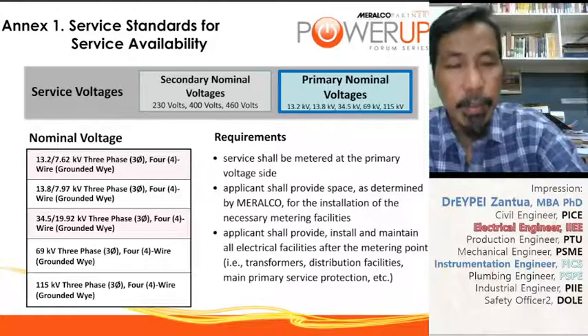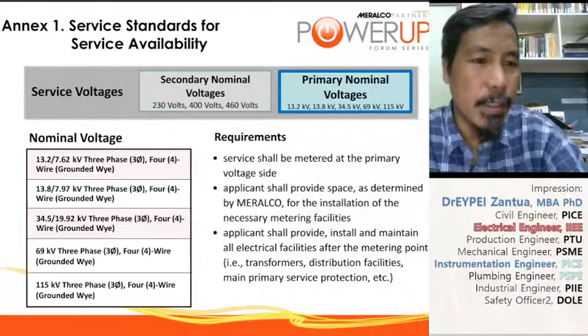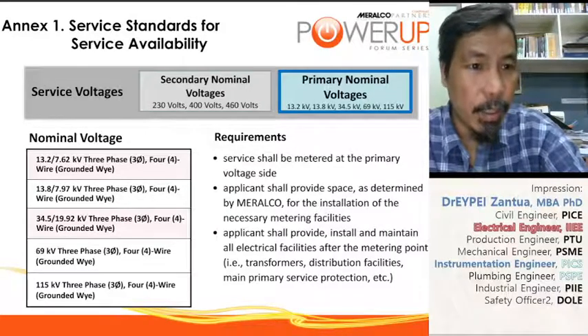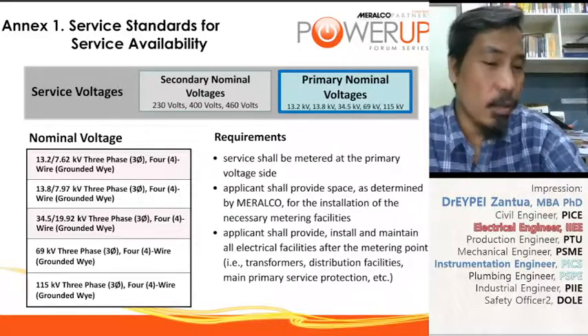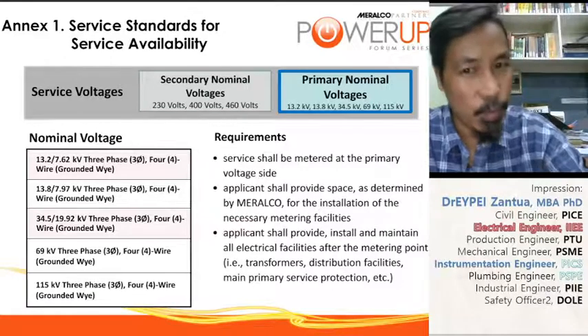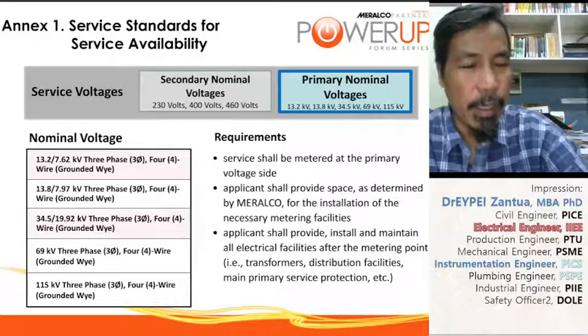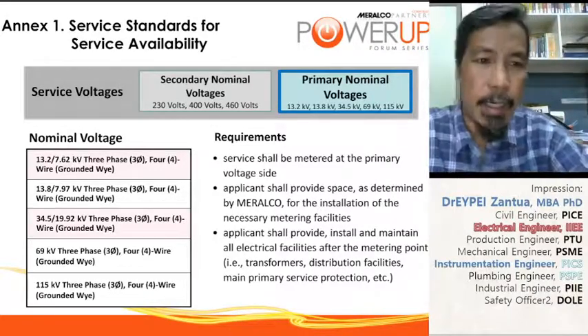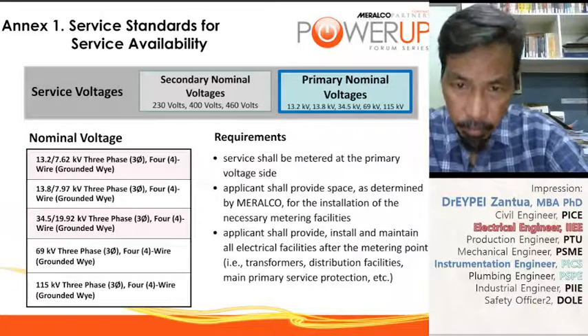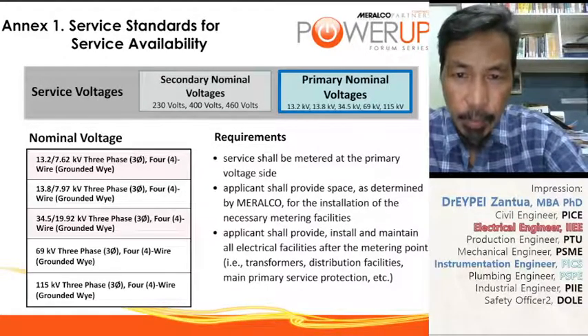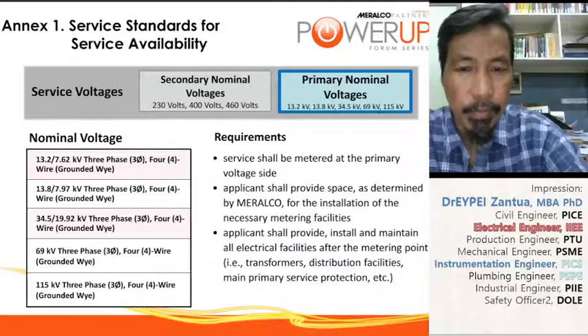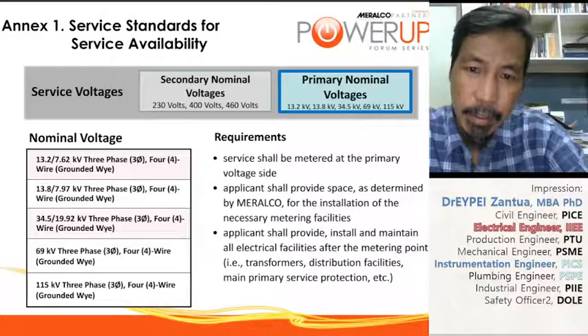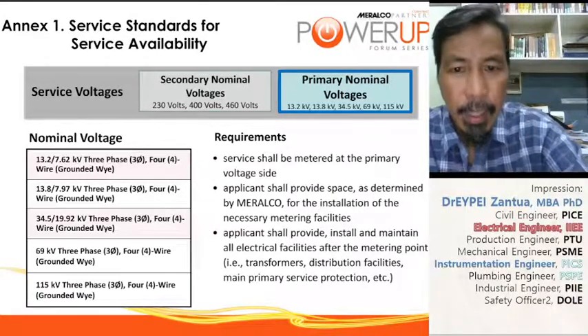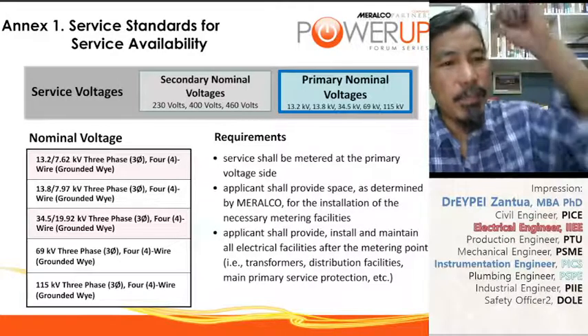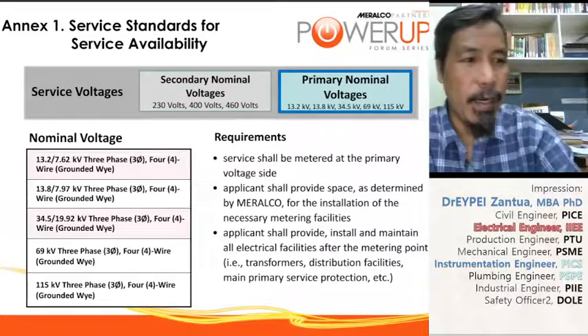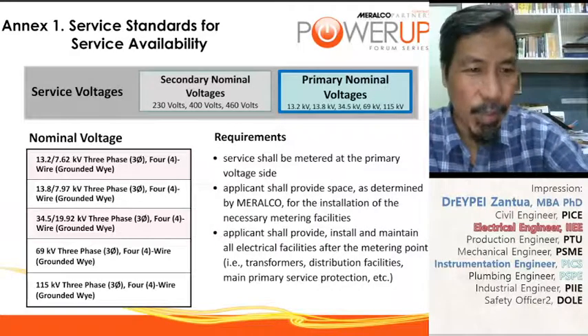Applicant shall provide space. So these are the situations where the client or the customer will have its own transformer or substation. Okay? They will just ask for primary nominal voltages. They are the responsible party for the secondary side. Okay? The applicant shall provide spaces determined by Meralco for the installation of necessary metering facilities. Applicant shall provide, install, and maintain all electrical facilities after the metering point. So they will just give you the wire and you will connect it. Okay?